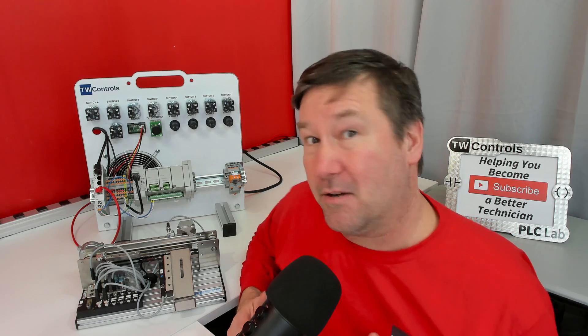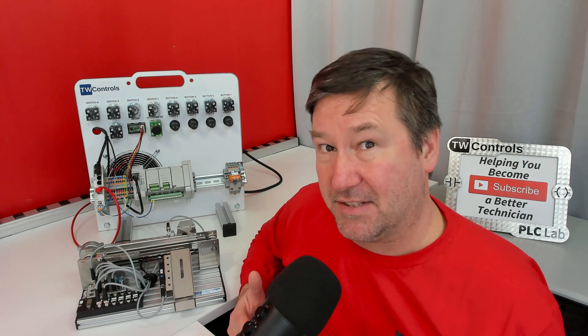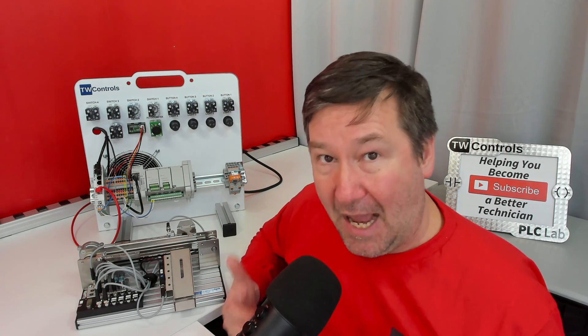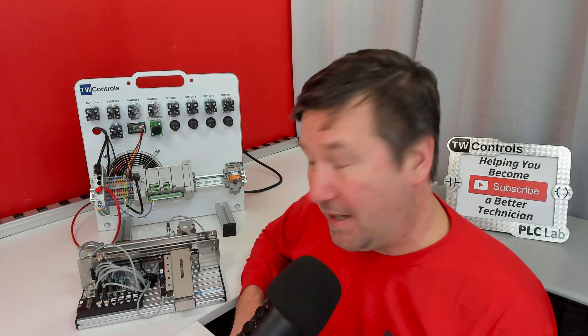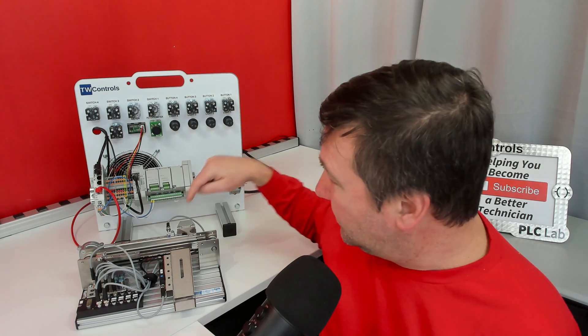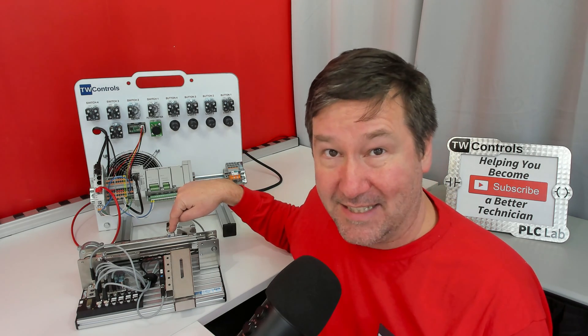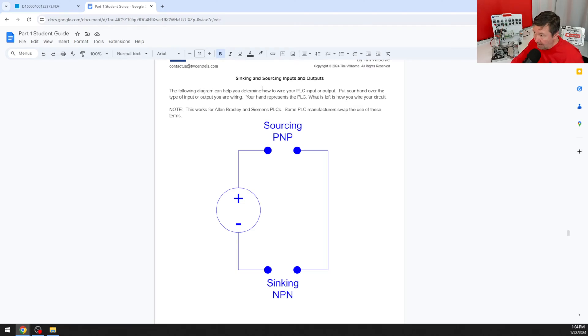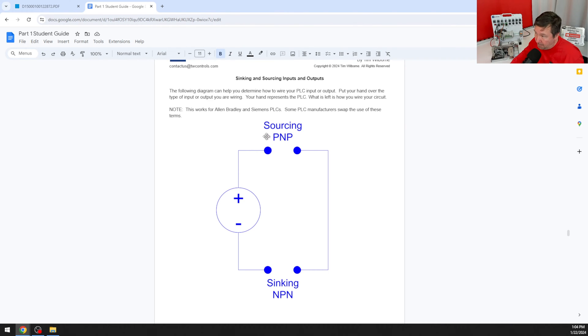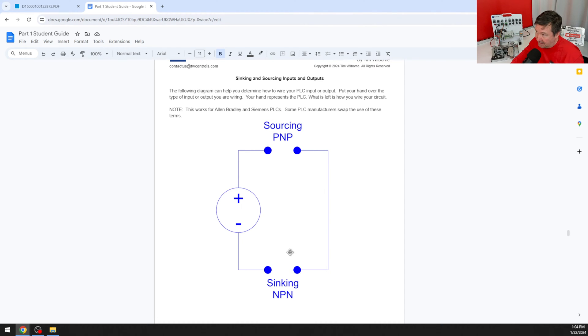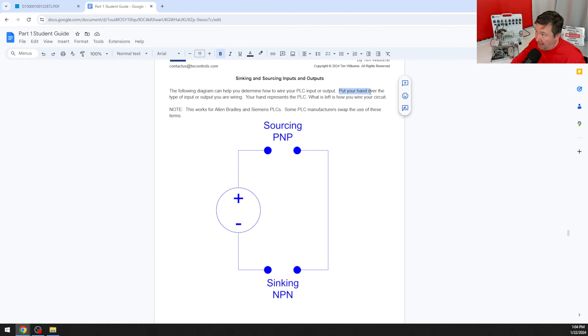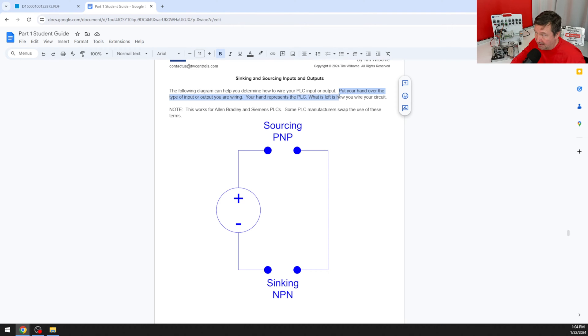The next thing we need to know is what type of sensors and what type of output loads do we have. These are PNP sensors and going back to our diagram from our sinking and sourcing video, if we have a PNP sensor then our PLC input is going to need to be sinking. I'll put a link to that video at the end of this one but put your hand over the type of input or output you're wiring. Your hand represents the PLC. What's left is how you wire your circuit.